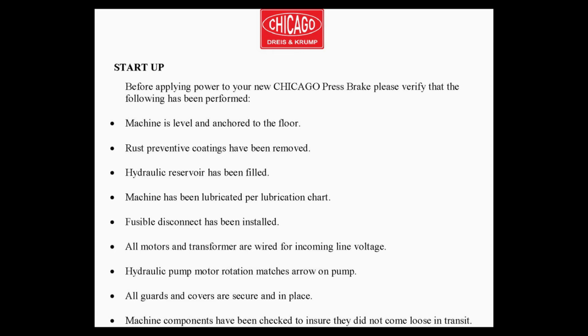Also make sure you have a fusible disconnect, which has been installed by a certified electrician. All the motors and transformers have been pre-wired for the requested voltage when the machine was ordered. So check your invoice and make sure you're hooking it up to the right voltage. It's either 220 or 440.